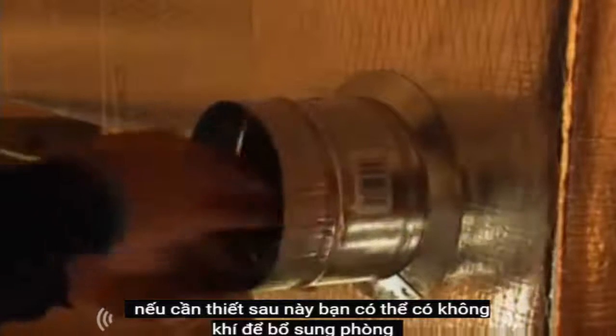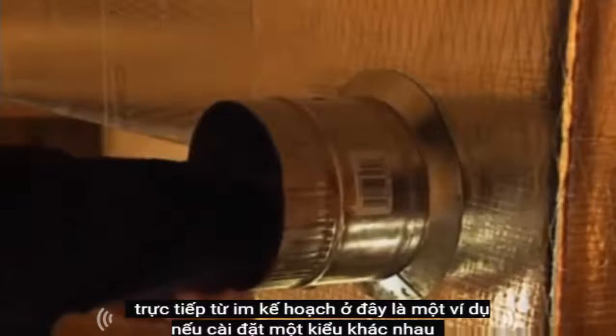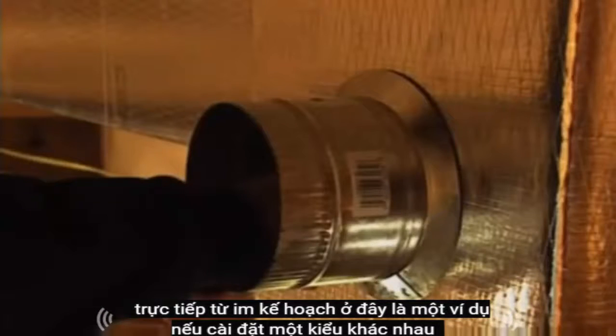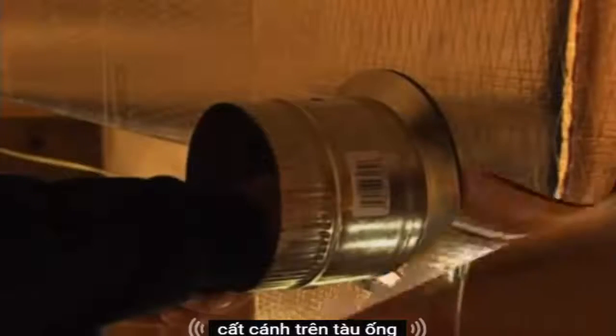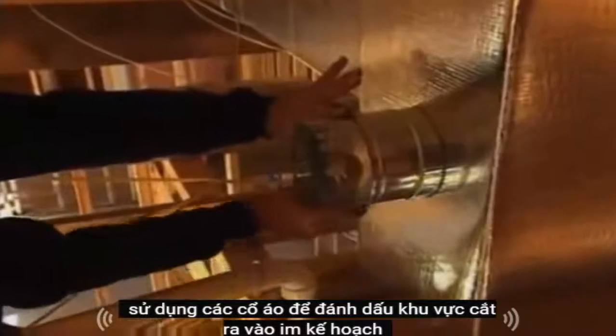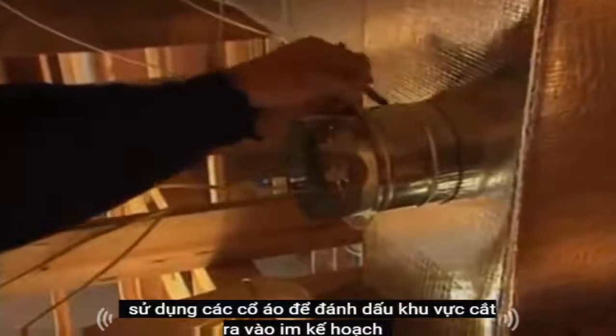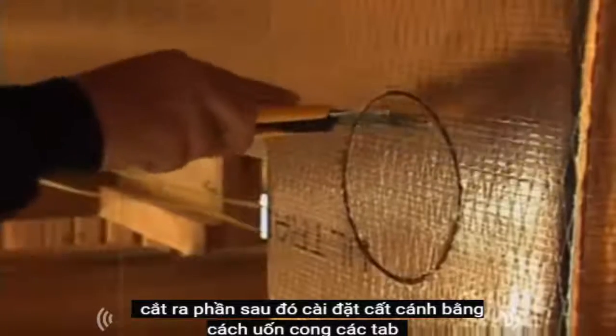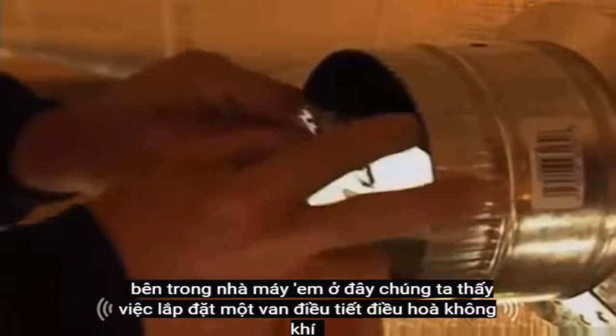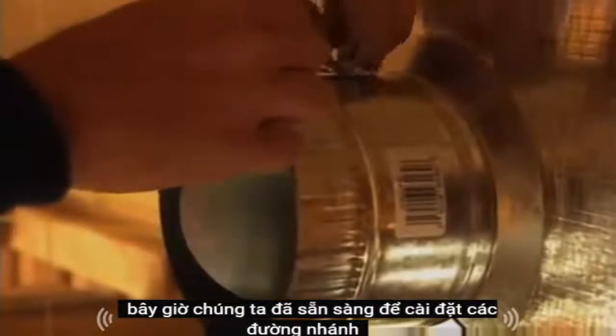You can take the air for your room addition directly from the plenum. Here is an example of installing a different type of takeoff on ductboard. Use the collar to mark the cutout area on the plenum. Cut out the section. Then install the takeoff by bending the tabs inside the plenum. Here we see the installation of a damper to regulate airflow. Now we are ready to install the branch line.